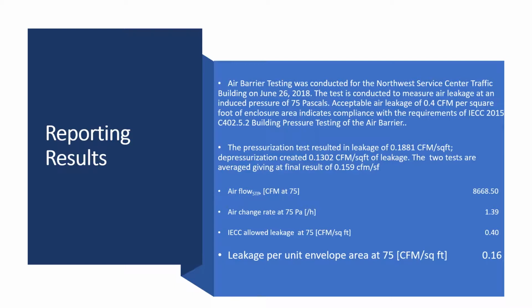We took a deep pressurization, depressurization. The full program adds the two together and takes the average. So we had 0.1881 on pressurization, 0.1302 on depressurization. So we add those together, average it. It comes out to 0.159 CFM per square foot. So the leakage airflow was 8,668 cubic feet per minute.